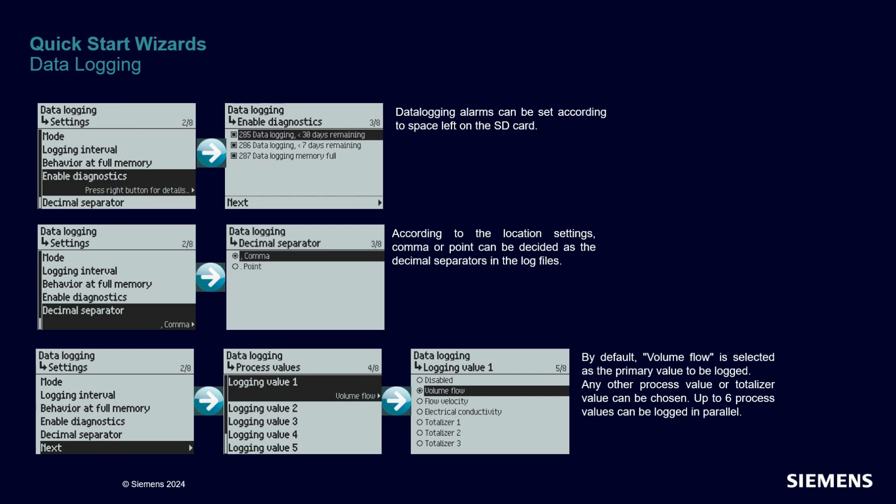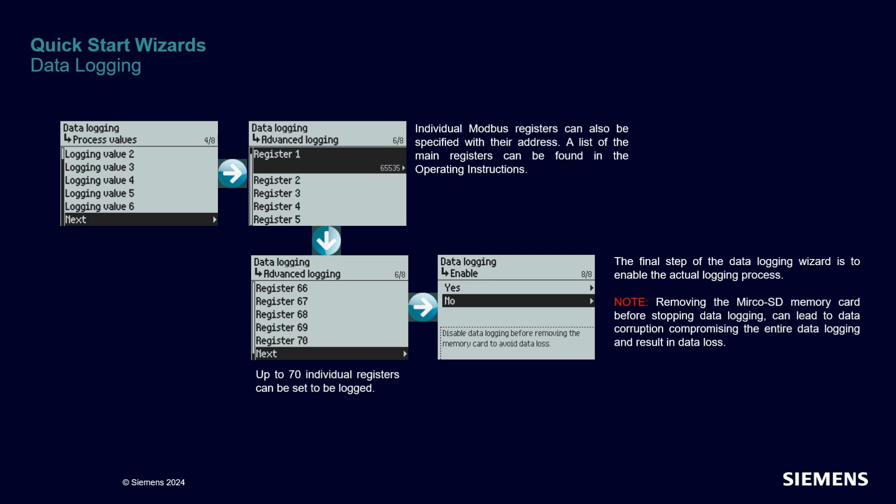Let's review the main settings of the data logger engine. You can select when you wish to be informed that the SD card is getting full, in order to receive a signal that you need to retrieve the data. In creating the log file, you can separate the desired values by either a comma or a point. Each log value can be selected individually. You can also choose to log individual Modbus registers by specifying their addresses — you can log up to 70 parameters this way.